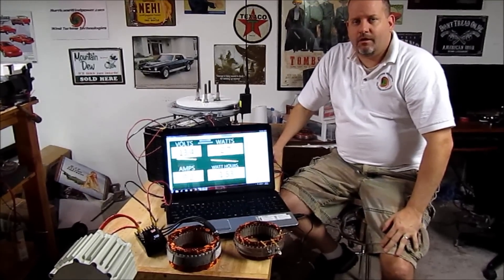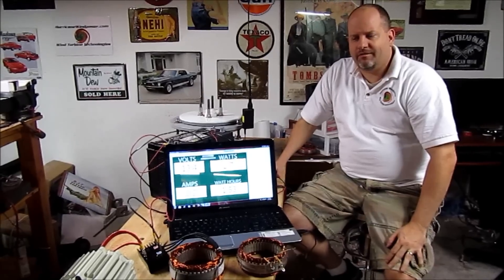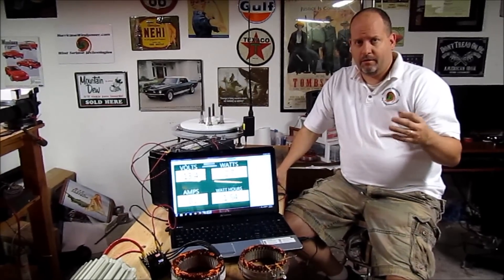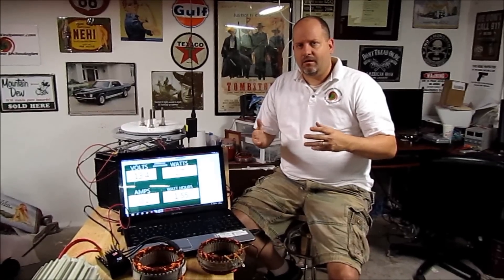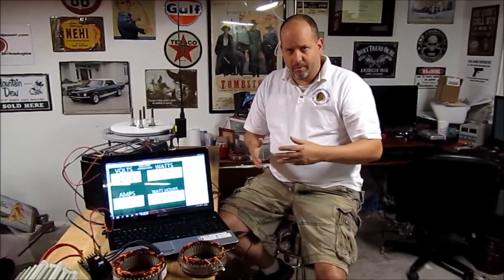Today I wanted to talk about wind generators, their components, and what you should be looking for when picking out a generator or a blade set, whether they come in a kit or as individual components. One of the most important things is that your wind generator needs to exceed the voltage of whatever it's charging — whether that's 12, 24, or 48 volt, or feeding a grid-type inverter. This exceeding of voltage, what we call the cut-in point, is important because until you reach it, you're not making any usable power.